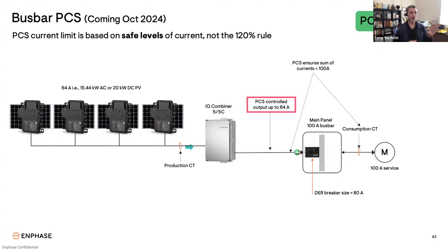Now, in this scenario, the only time the power output would be curtailed is if the home's electrical loads were drawing so much current that the main breaker would trip. In other words, it would be extremely rare and probably never happen that the system would be curtailed. So again, just to be clear, we're talking about installing up to a 20 kilowatt DC PV system on a 100 amp panel with power control system and without having any impact on energy production of that PV system. It's quite remarkable.